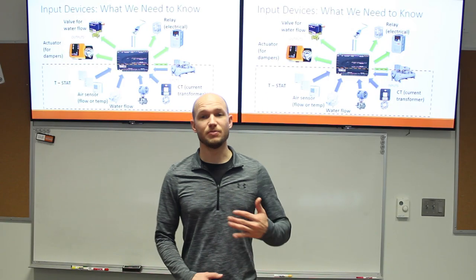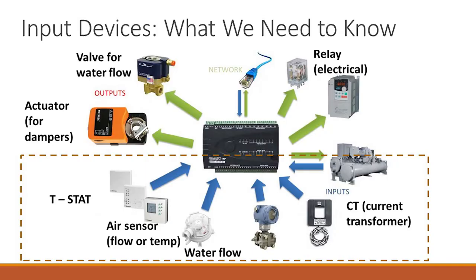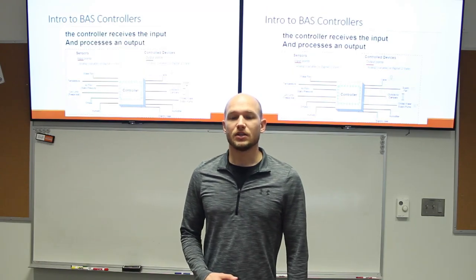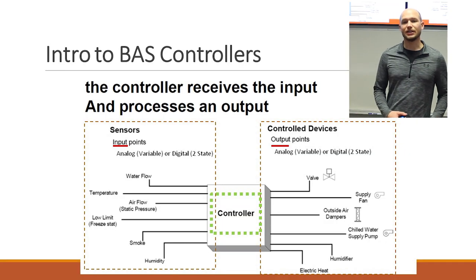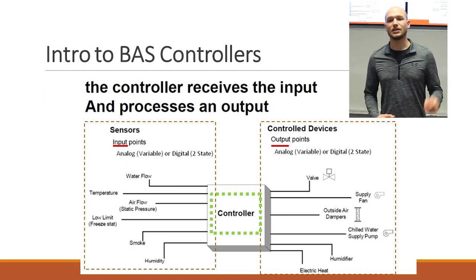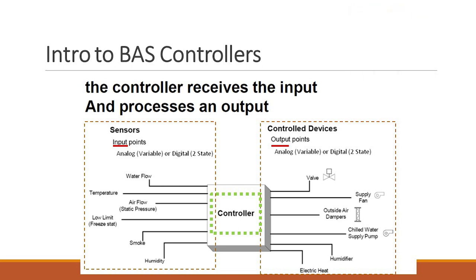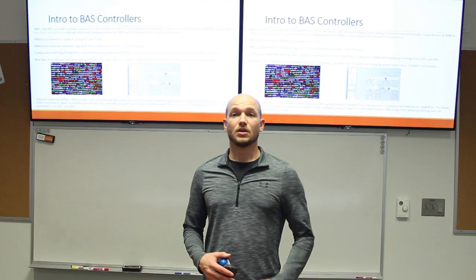Input devices — what does the controller need to know? This information comes from thermostats, air sensors, water flow, current transformers, and inputs from different machines. In this picture it's a chiller. The controller receives the inputs — you can see the input points in this box — and then it outputs. That output can be a valve, a supply fan, or a damper.